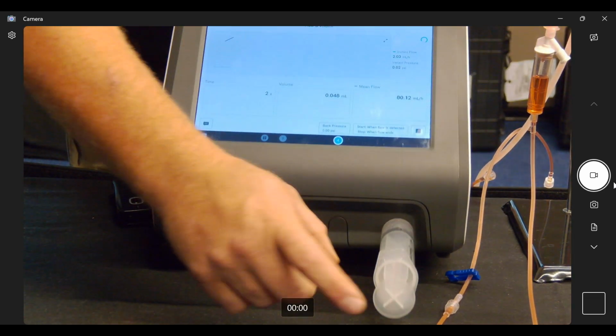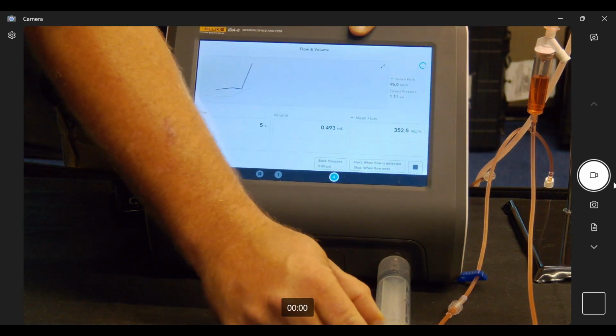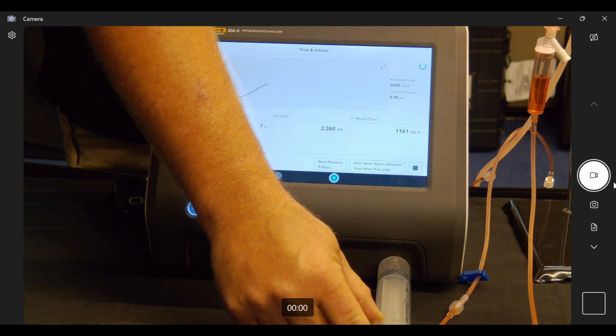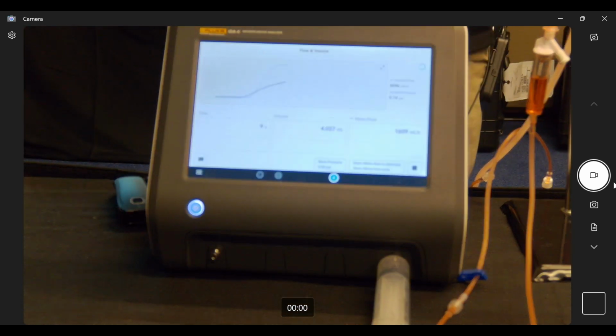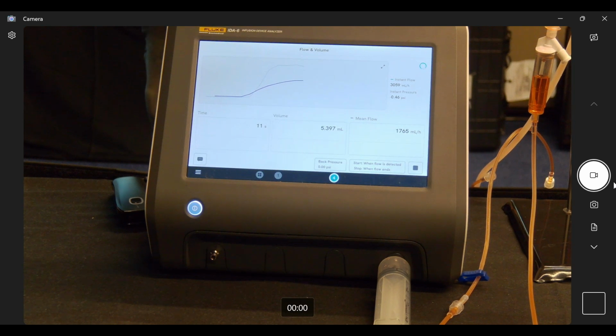And even with pure air, we can sense a flow. So the issue with air bubbles is now gone as well. You don't need to run cleaning solution through it because there's no glass pipettes or photo eyes to try to keep from occluding.